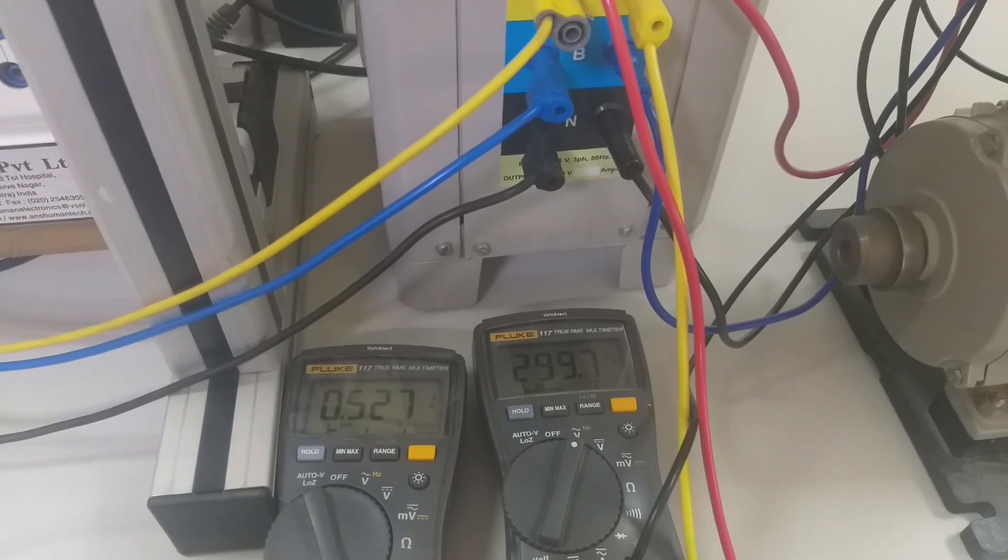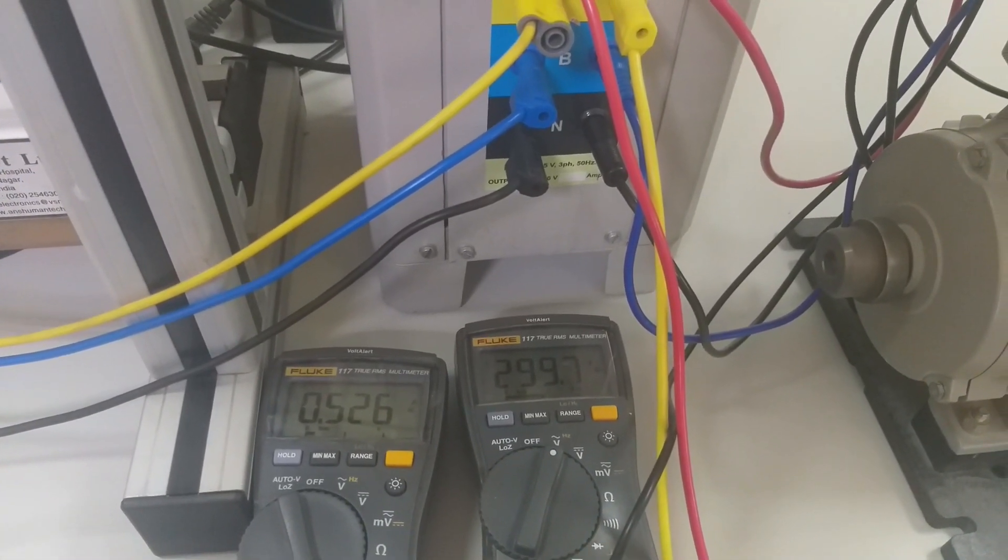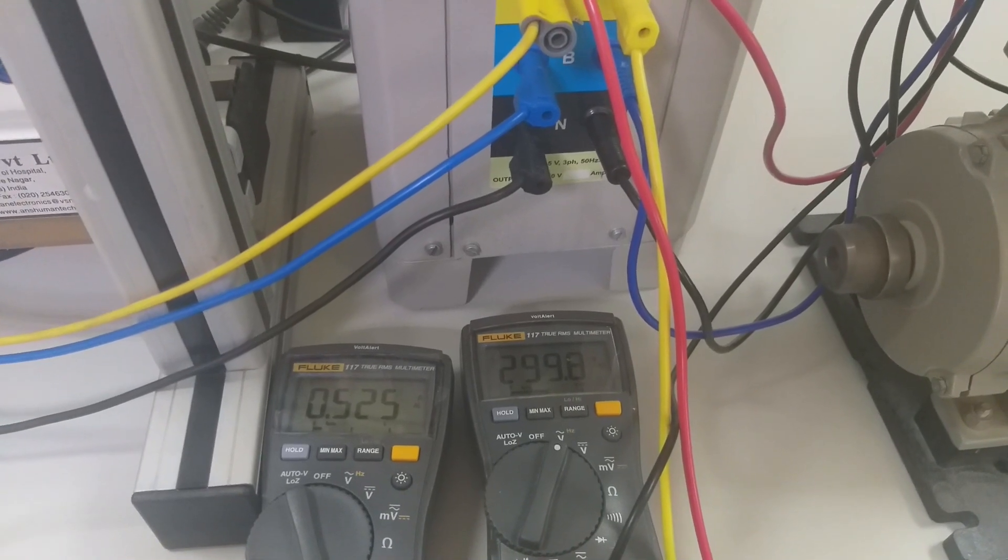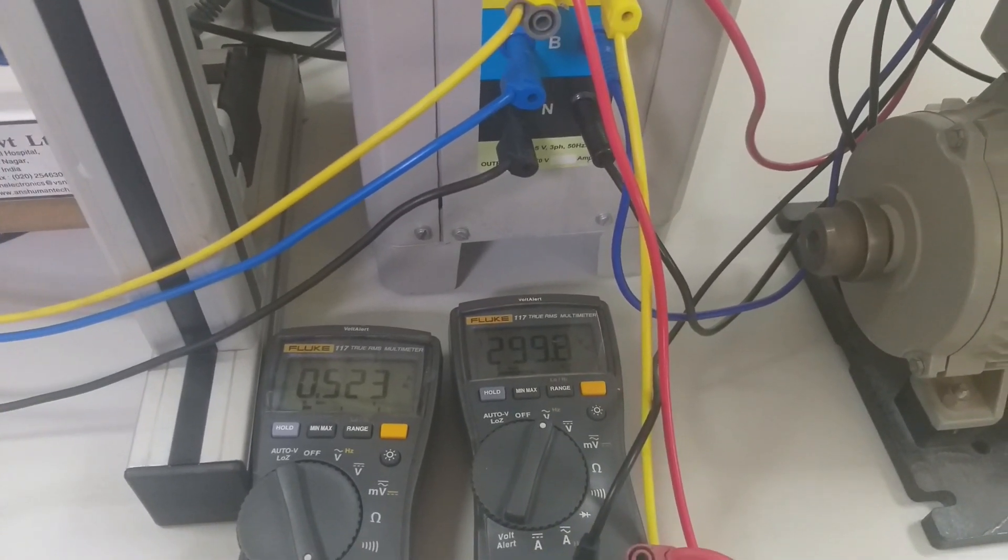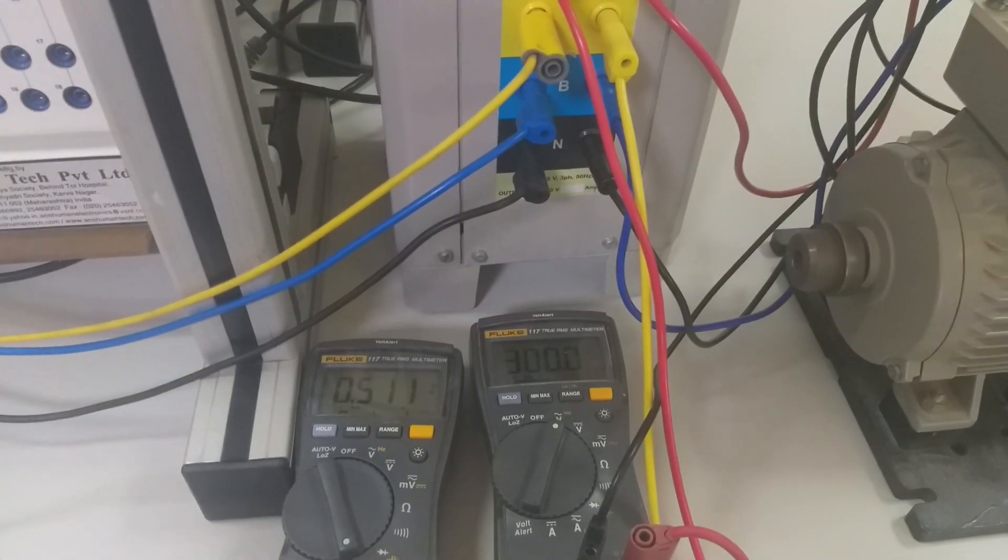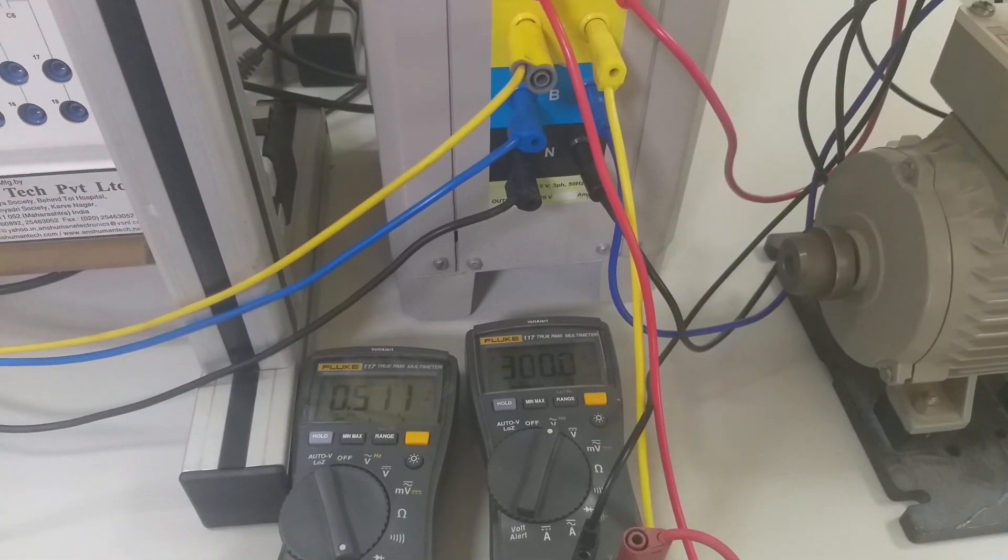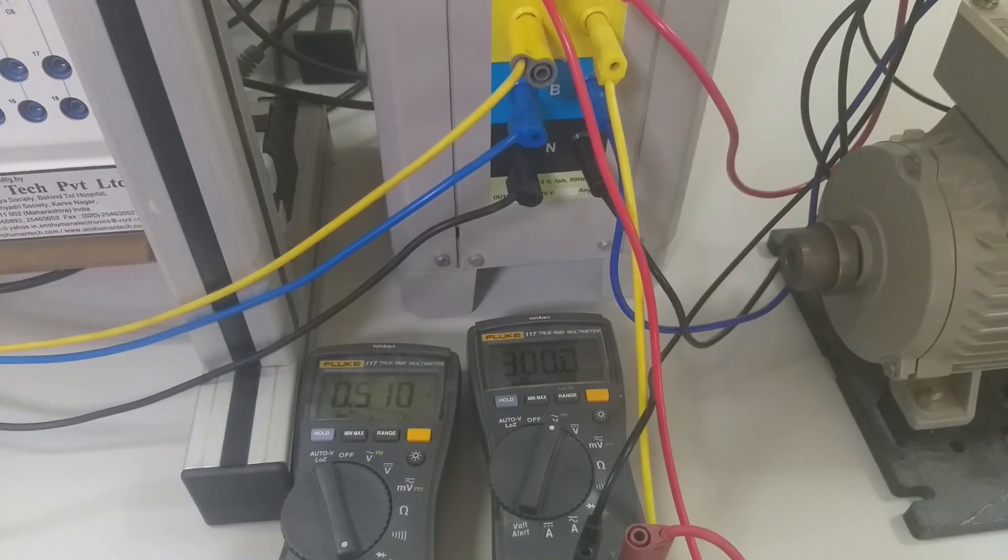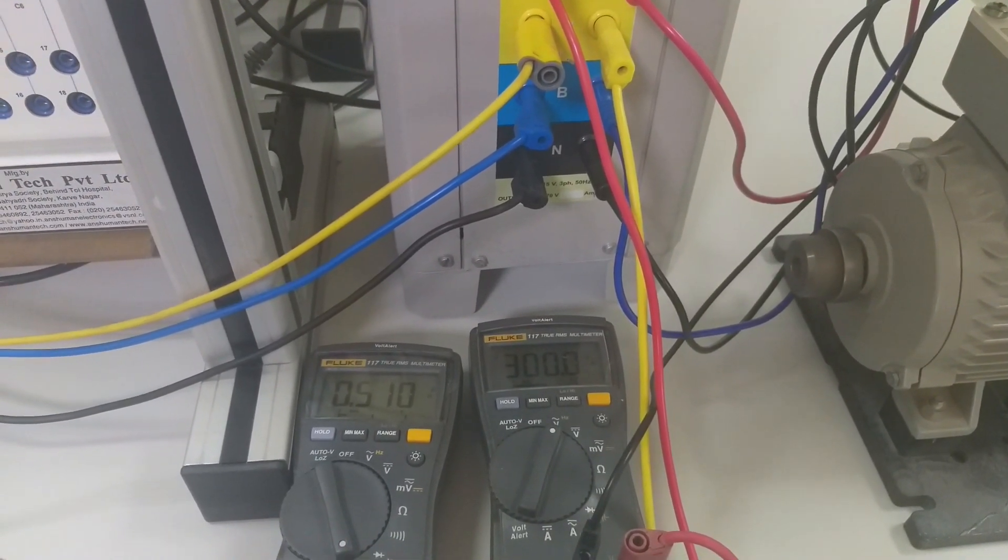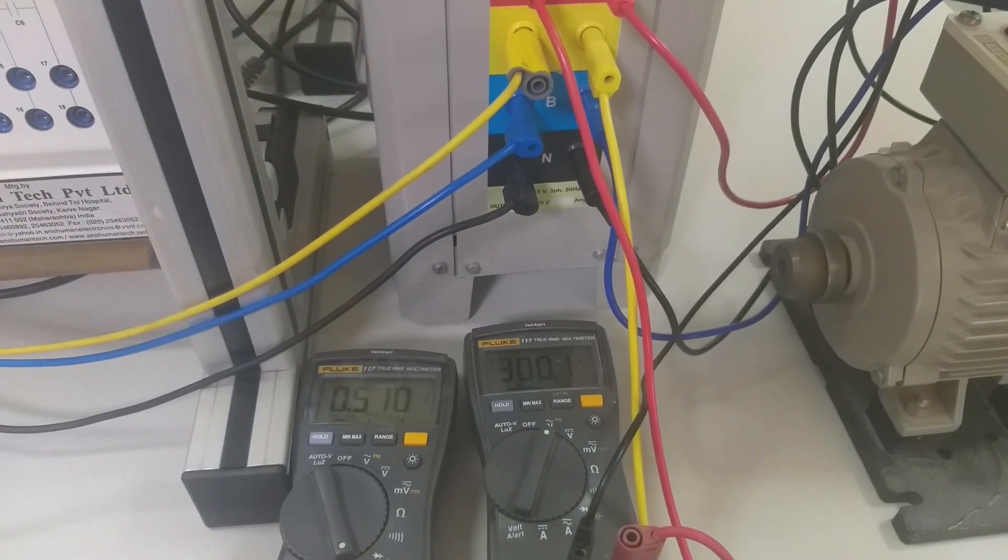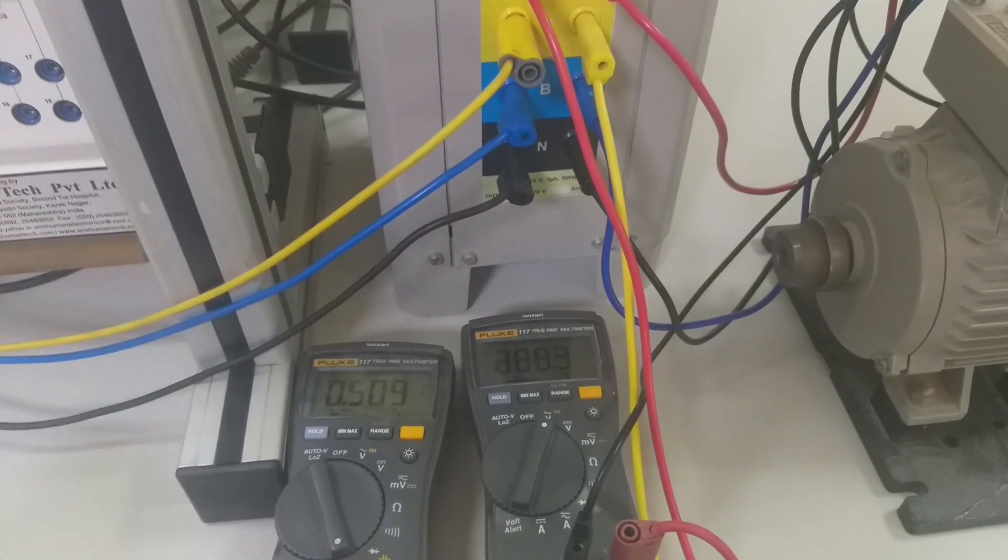So I set 300 volts for the same voltage. Now you can see the current is 0.524. But now to reduce this inrush current or the starting current, we are going to apply this mechanism to increase gradually the applied voltage. So by reducing the voltage, we are going to reduce the current. So that is the simple theory behind this auto-transformer starter. Thank you.